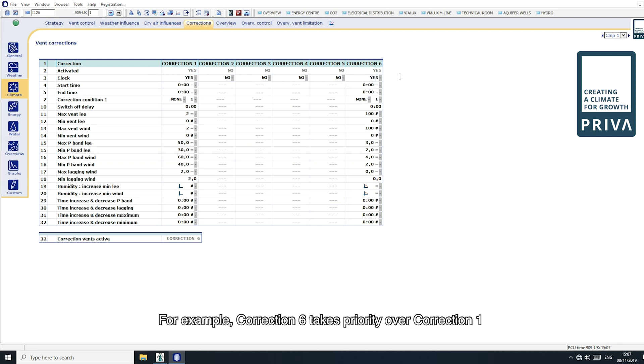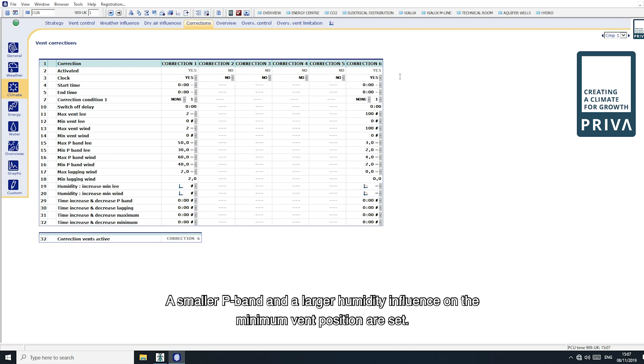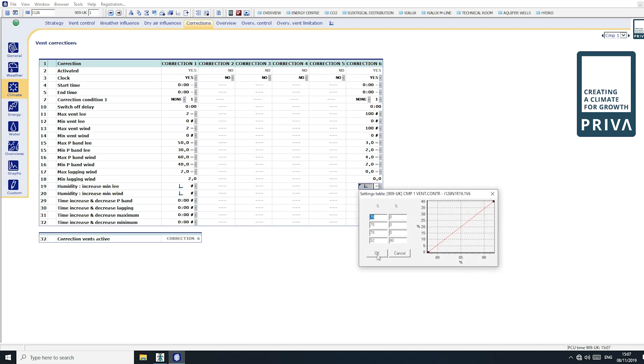For example, correction 6 takes priority over correction 1. Correction 6 is used when the curtain is closed. A smaller p-band and a larger humidity influence on the minimum vent positions are set.